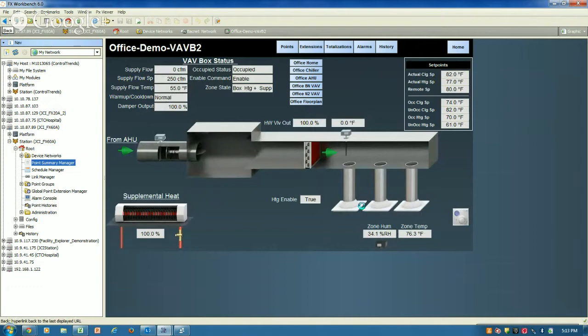So if I wanted to put this on my home page, an operator could come in the morning and check all of his VAV boxes at once. The real power is that there might be things you don't get an alarm on because it's not out of whack, but something might still be out of control. For instance, if you've got a bunch of rooftops all in cooling, but one of them is in heating, that's not really an alarm, but at least you could view that all from one screen, especially with multiple units.